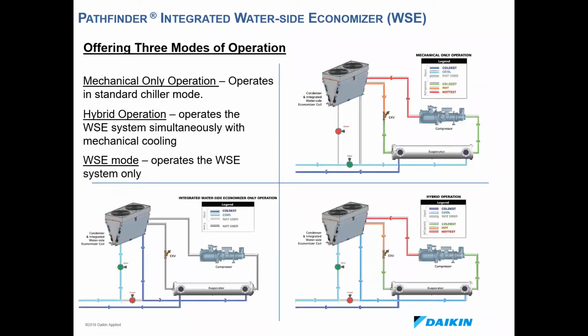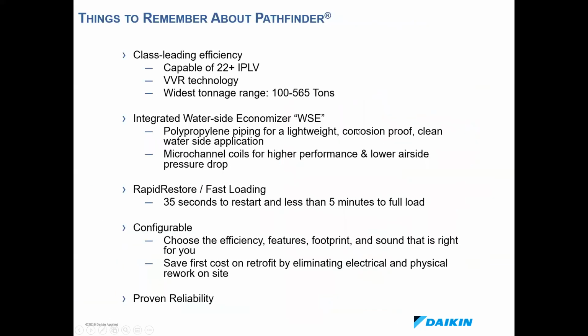Real quick, we'll go over the operation of free cooling. You've got three modes: mechanical, hybrid, and water side economizer mode. The top right is mechanical mode, which is what you're used to, just your refrigerant running through your compressor and evaporator and condenser coils. In hybrid operation, you're first diverting the flow through the free cooling coils to pre-cool the fluid for the evaporator, which will make your compressor not have to work as hard. And then in integrated water side economizer mode, or free cooling mode, you're bypassing the mechanical section completely and going only through the free cooling and the evaporator. The chiller controller is going to be operating these valves based off of ambient temperature, so no intervention would be required there.